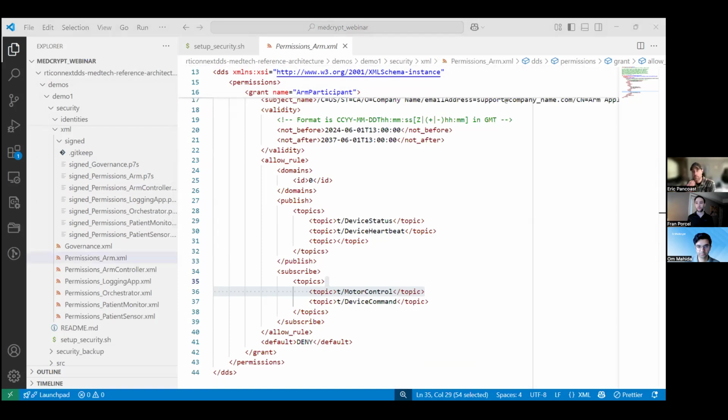And I guess to comment on what that means for medical device engineers, in terms of not only implementing the RTI Connext solution, but also the proper security behind it, there are all those pieces that we talked about earlier in the demonstration. Your infrastructure with the HSMs and the PKI and the provisioning workflow system. Controlling the crypto library on your device so that you can generate those unique keys, generate the CSRs, usually more than just one of them, right? To transfer up into the provisioning workflow system to get your certificates back on the device so that it can operate securely.